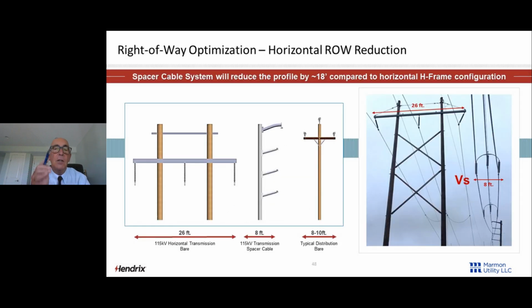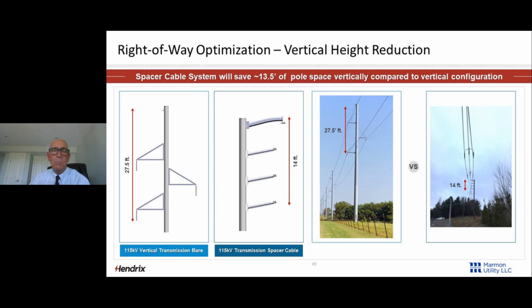How about if we took a look at, on the left, you've got a horizontal bare wire construction on an H-frame. So that's about 26 foot side to side with 115 kV spacer cable is 8 feet. So we're saving 18 feet on the width of that right of way. Not only are we saving 18 feet, but our 115 kV is taking about as much space as a typical 15 kV line. So we're talking different stuff here.